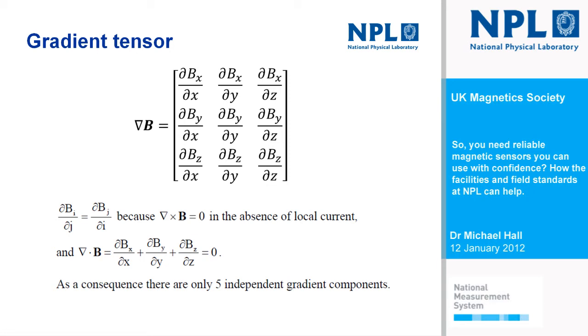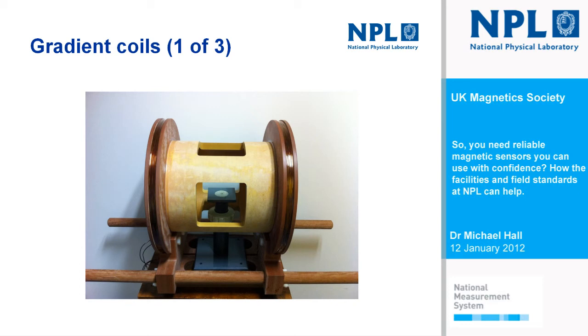Something of interest to note here is the winding that we have on each of these formers. The conductor there is capable of carrying up to 20 amps. The target field gradient here was 50 microtesla per meter, but we need much more current to generate higher fields so that we can actually calibrate that Helmholtz, so that gradient coil system, using a very small sensor so that we can get the spatial resolution using a Hall probe. So we need to pass 20 amps through. In practice, when it's being used, we're probably only putting a couple of 100 milliamps through to generate the gradients that we need. And the gradiometer would sit here in the center. So we have 50 microtesla per meter as the required.